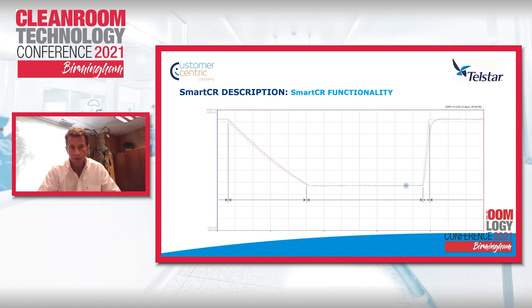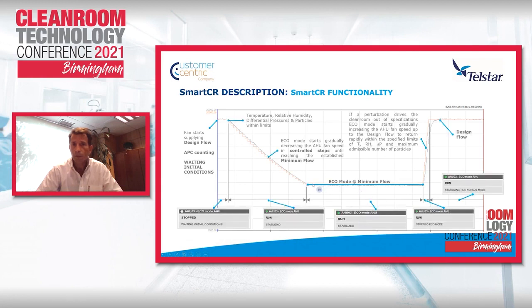As said, you cannot change the supply airflow in one step immediately, because the balance of airflows among the different rooms, that means the balance of the differential pressure in the different rooms, can become unstable for an unaffordable period of time. So what we design is a rundown time, 2 parameters that will be fixed during startup and commissioning, which we will see now. Then we have a kind of eco mode, which we call minimum flow, which will also be set during the startup, commissioning and qualification.